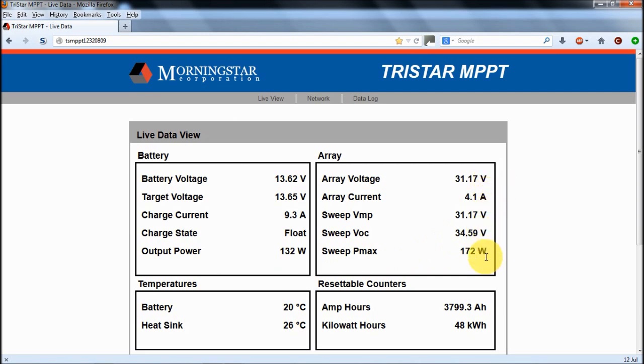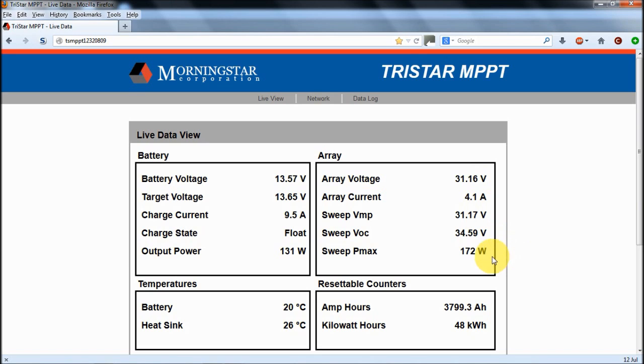These sweep parameters show what the power point tracker had identified. So it was finding that this was the open circuit voltage, this is the voltage from maximum power point, and you'll see that it's operating close to that at the moment. And this was the power that it identified could be delivered last time it did a sweep. Interestingly, the time between sweeps can vary according to what the power output of the controller is and what's going on.